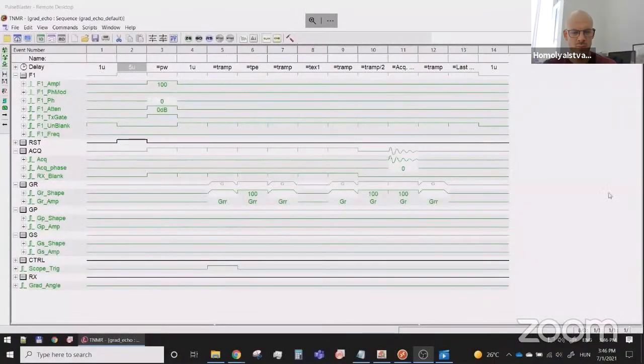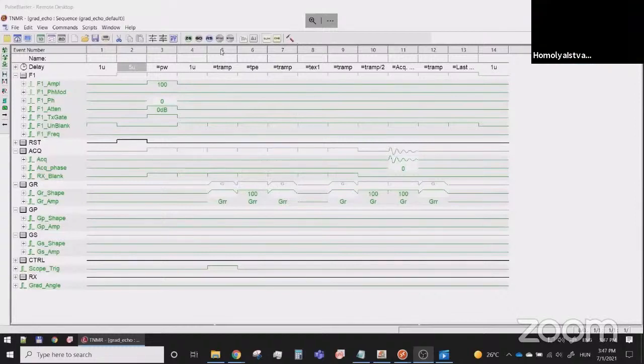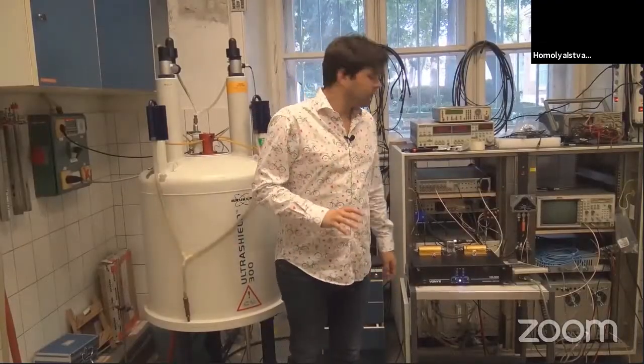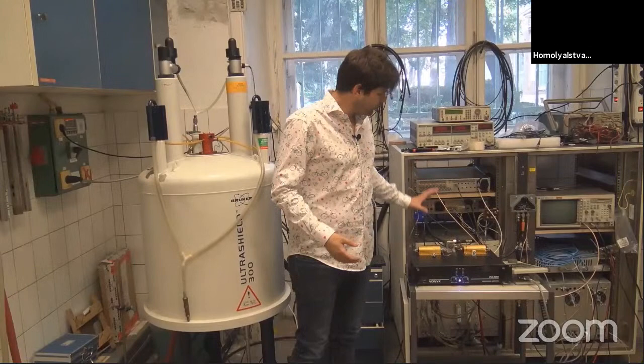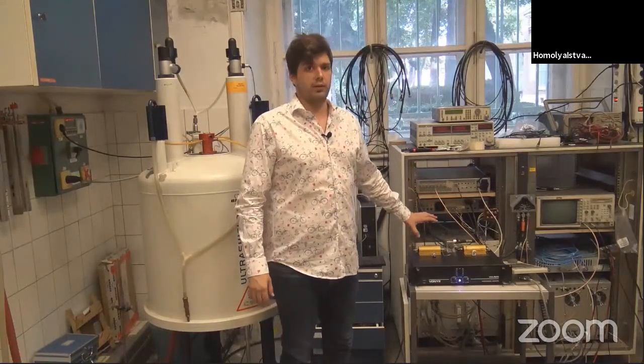In this experiment, we use a small object consisting of 3 × 3 holes filled with simple tap water. Such a sample that imitates an object under study is called a phantom. We can now perform the experiment with a suitable pulse sequence. Such a pulse sequence consists of a radio frequency pulse shown in column 3 and some gradient pulses shown after column 5. The so-called gradient echo can also be generated while applying a magnetic field gradient along the x-axis. The gradient magnetic field in the x direction is produced by this. This is called a gradient line.